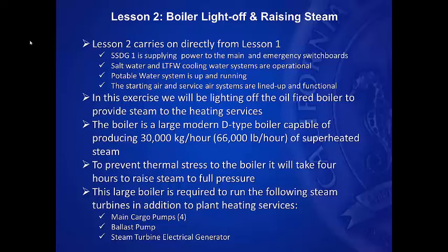In this exercise, we will be lighting off the oil-fired boiler to provide steam to the heating services. The boiler is a large, modern D-type boiler capable of producing 30,000 kilograms per hour of superheated steam. To prevent thermal stress to the boiler, it will take 4 hours to raise steam to full pressure.